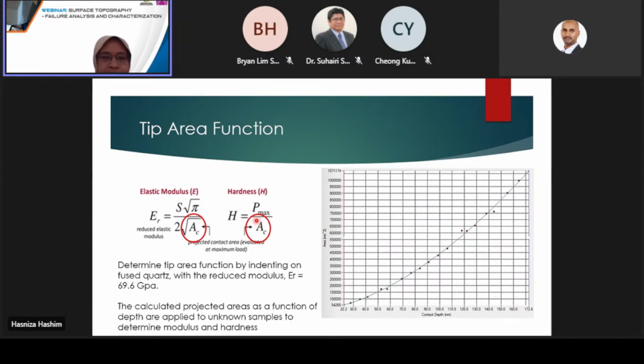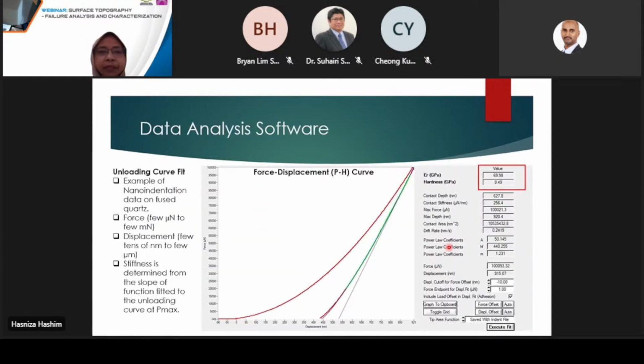So what we did here is a series of indents at various contact depths, with varying normal loads performed on fused quartz, and then the contact area and contact depth are calculated. By calculating the projected area as a function of contact depth on known samples, we can then apply it to unknown samples to determine the modulus and hardness.